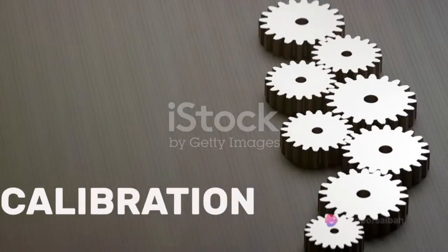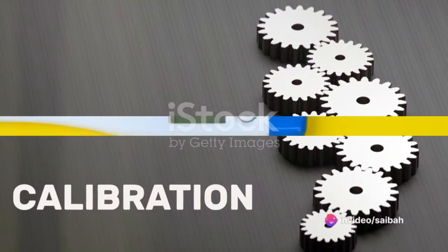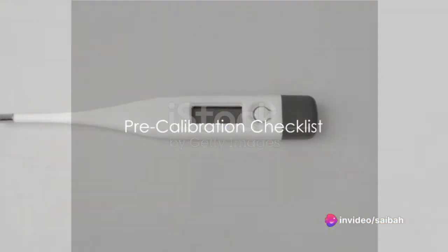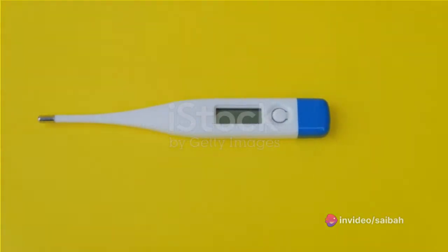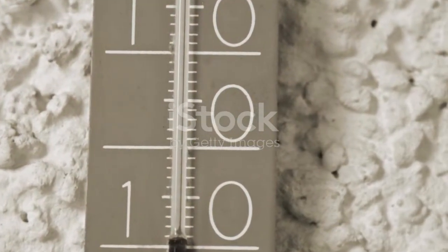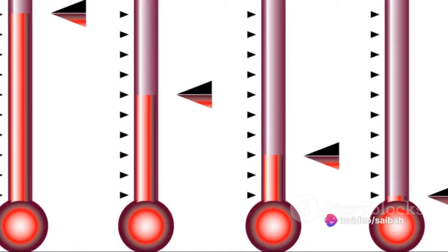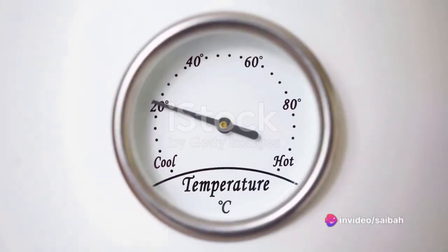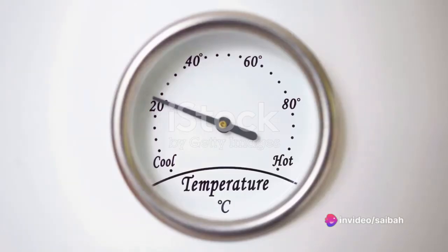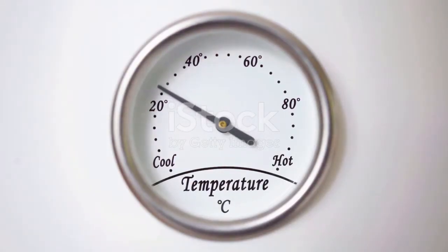Now, let's dive into how you can calibrate this essential device. Before you start calibration, ensure you have the right equipment. Having the correct tools in your arsenal is a critical first step in calibrating a temperature switch. So, what will you need? First up, a calibrated thermometer is essential. This will act as your benchmark, providing accurate temperature readings to compare with those from your temperature switch.